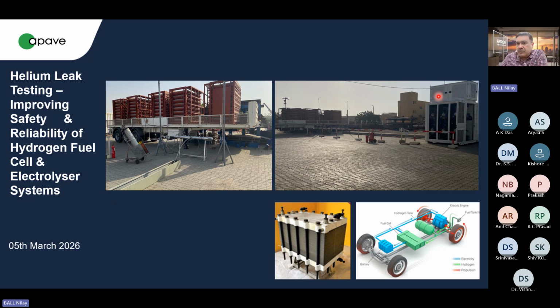And in the next 1 hour, we found that the pressure had dropped from 30 bar to 12 bar. And that was raising an alarm. It was a visual perception that we saw the pressure falling, but there was no alarm from the hydrogen sensor inside this fuel cell, because the air vent system was so well designed that the inside leakage was pushed out by the exhaust fans. So this is the second line of defense. The question is, if the leakage is there and you have a very good exhaust system, then you can avoid any sort of accidents.